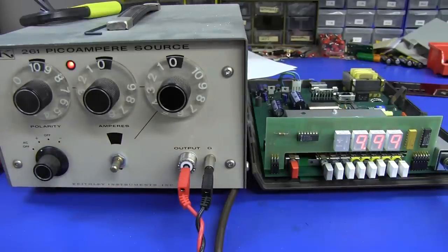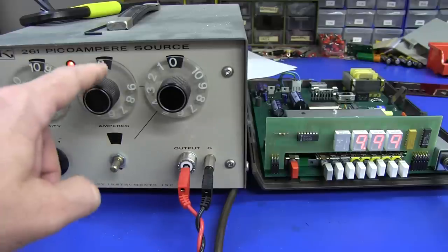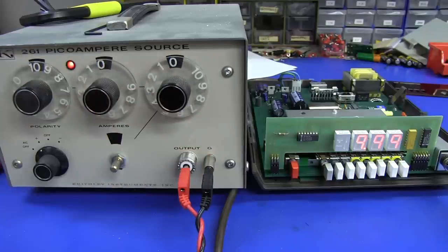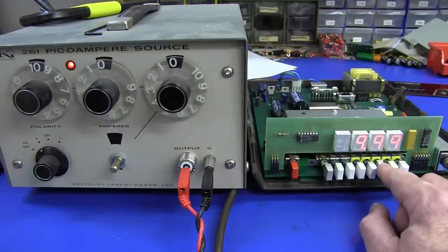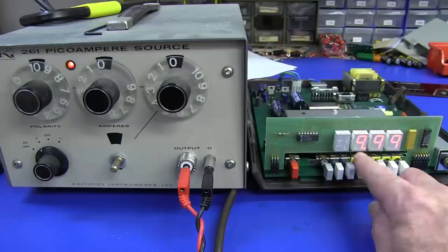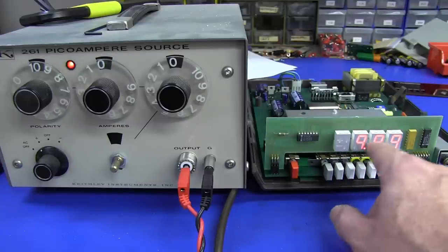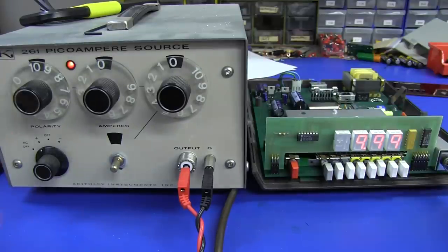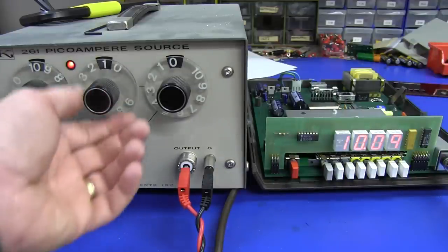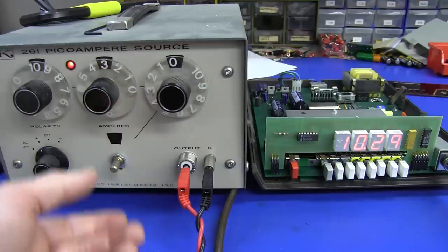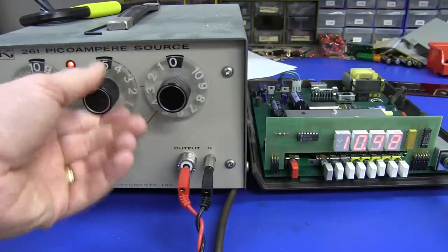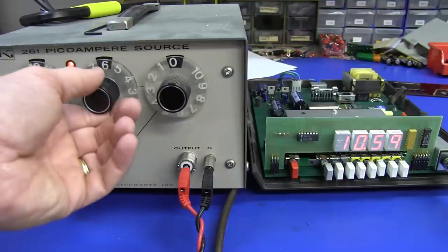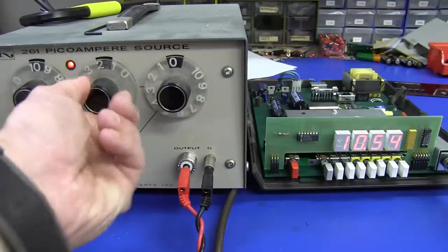Anyway, what I've got this thing on is the 10 microamp range, so it's 10.00 microamps here, and I've got it on the 10 microamp range here, and there it is, 9.99. You saw it before, it was 10.00, so something's drifted somewhere a little bit, but it's basically spot on, and we should be able to tweak that. There we go, look at that. Just dial it in. We're only one least significant digit out between these two units.